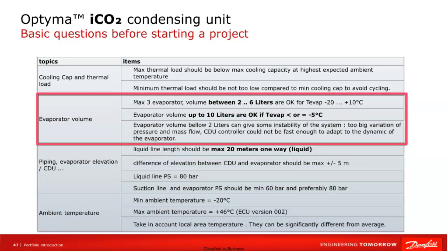Evaporator volume. Restrictions related to filling the refrigerant. For example, there is no problem with the volume of 10 liters at a temperature of -5 degrees Celsius. However, a larger charge may pose a risk of loss of refrigerant under certain operating conditions. Pump down operation should not be used with evaporators with a volume of less than 2 liters, to avoid very low suction pressure during the final pump down stage and excessive discharge temperature.